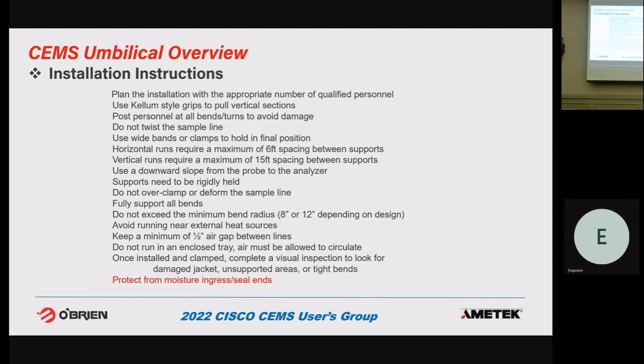And we require that on any vertical installs more than 50 foot. So when you're pulling it into place, we want to use those Kellum grips and attach the cable or rope to the Kellum grips to pull it into place, not tying a rope around the bundle and compressing that thermal insulation. So don't twist the bundle, use wide bands or clamps to hold it in the final position. The supports on horizontal runs, no greater distance than 6 foot, and on vertical, no greater distance than 15. So we want those supports at that distance or closer, mainly to keep it from moving around due to the wind.